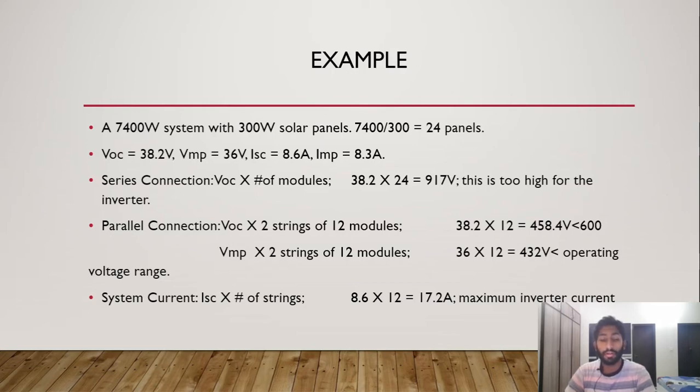For a parallel connection with two strings of 12 modules each string, you multiply Voc with 12, so Voc is 38.2 times 12 modules equals 458.4 volts in one string. You have to check that with the maximum input voltage for the DC inverter - in our case I've chosen 600 volts, so that's less than 600 volts, so that will meet and that will work.